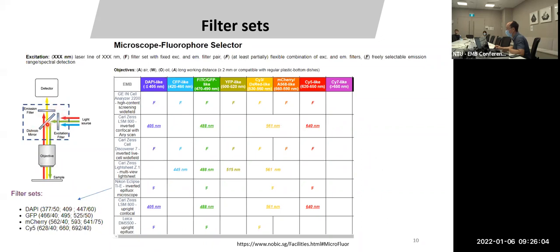But if you want green and you collect it in red, then you have to look for microscopes that have these three elements separated, right? So these are highlighted in asterisks here. All these microscopes have this flexible combination where these three elements are not in the same filter cubes. But for the very basic one, usually they are on the same filter cube.